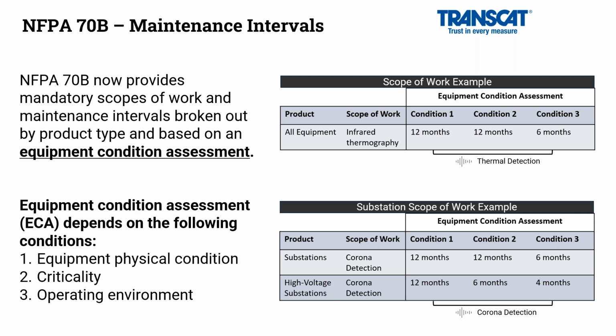Or maybe I'm doing corona and partial discharge on that substation or that switchgear or that motor control center to determine if we have electrical breakdown of the insulation, and it's starting to show up in the form of an electrical arcing event that is picked up as a high frequency event with something like an ultrasonic leak detector. So starting to get an idea where this is going.